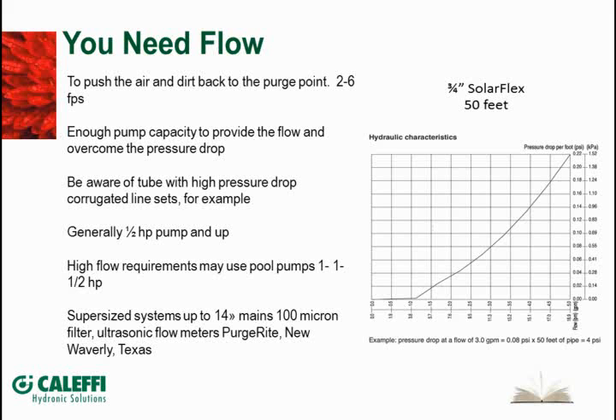My question to them was, how do you know when you've got enough flow to be pushing air out? Because some of these systems, they didn't even know what they were getting into, because the systems were buried under a lawn or a parking lot. They didn't know what size loops they had or how many loops. What they would do is put ultrasonic flow meters on the piping so they could see the flow rate. If they saw they had an 8-inch main, they knew what flow rate they needed to get up to 4 to 6 feet per second to push the air back to where they could purge it out.